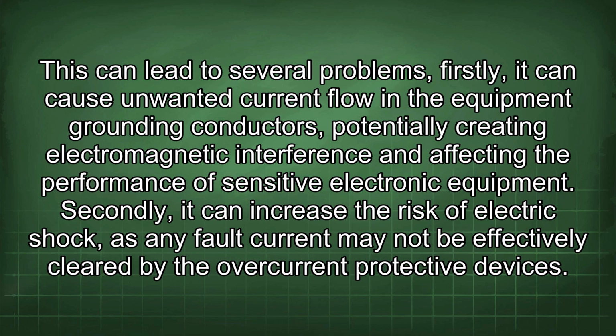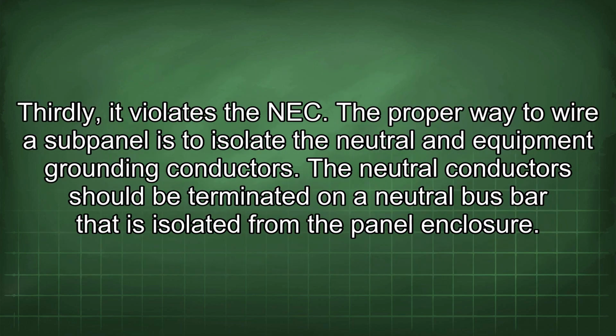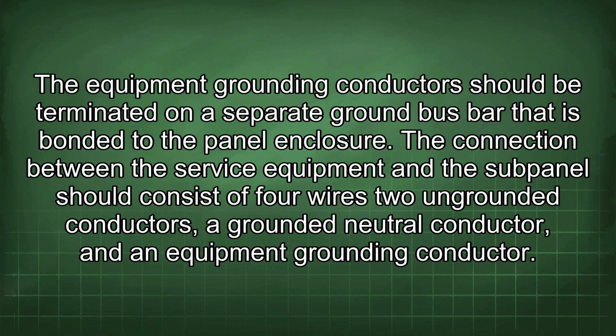Firstly, it can cause unwanted current flow in the equipment grounding conductors, potentially creating electromagnetic interference and affecting the performance of sensitive electronic equipment. Secondly, it can increase the risk of electric shock, as any fault current may not be effectively cleared by the overcurrent protective devices. Thirdly, it violates the NEC. The proper way to wire a subpanel is to isolate the neutral and equipment grounding conductors. The neutral conductor should be terminated on a neutral bus bar that is isolated from the panel enclosure. The equipment grounding conductor should be terminated on a separate ground bus bar that is bonded to the panel enclosure.